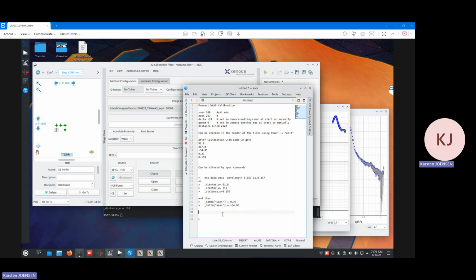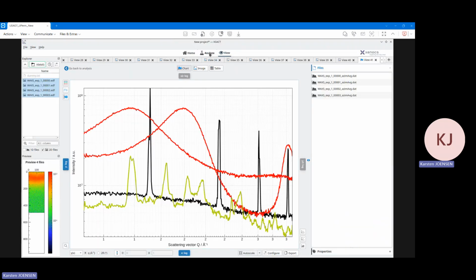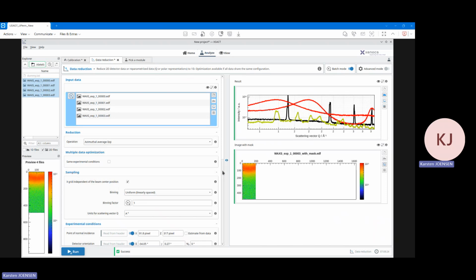And then here, this would be 34, 105, and 0.27. Now, as I understand it, the WAXS position may change. I believe it's A in this measurement here. I suppose it could be B or C as well. I'm not quite sure how to use that, but one could hardwire these if it turns out that it's always the same position. That would help a little bit. That would get you closer. On the other hand, if you change positions, you'll definitely need to run these to calibrate when you're running with the different configurations. But that's essentially how to use this. Again, I'm not too happy with these bugs that are in this program, but I'm confident that with these workarounds, the data that comes out is still correct.